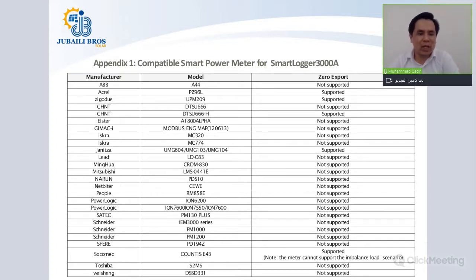Okay, so this is Appendix I, which we were speaking about in my slides, which lists the compatible smart power meters for the Smart Logger 3000A. You can see the first column is the manufacturer name, the second column is the model from that manufacturer that you can use, and the third column shows whether that power meter can be used for the zero export function or not. You can see that only the model PZ96L can support zero export. UPM209 can support zero export. Chint model DTSU666H can support zero export. And Janitza UMG 604 multiple models can support zero export. You can also have a SOCOMEC in your PV plant and do the zero export.